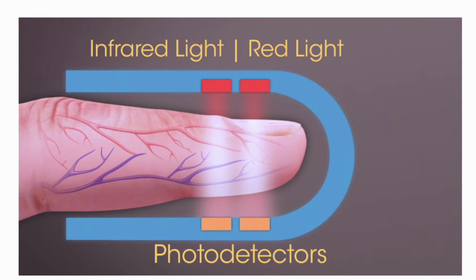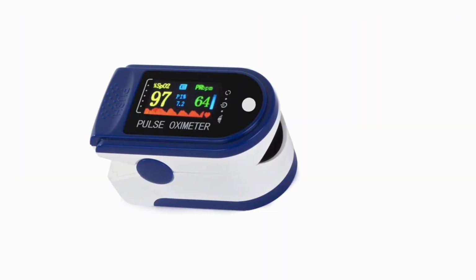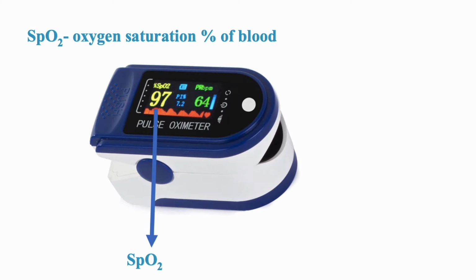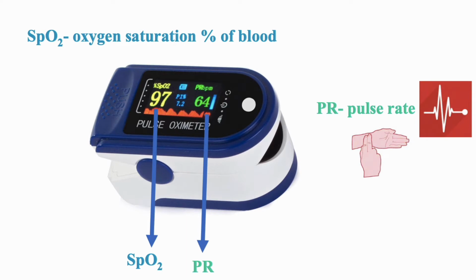Small beams of light pass through the blood in the fingers and measure the amount of oxygen. The changes in light absorption in oxygenated or deoxygenated blood are measured. There are two different readings shown on the pulse oximeter. First is the oxygen saturation percentage of blood, that is SpO2, and the next is pulse rate, that is the number of times your heart beats per minute.